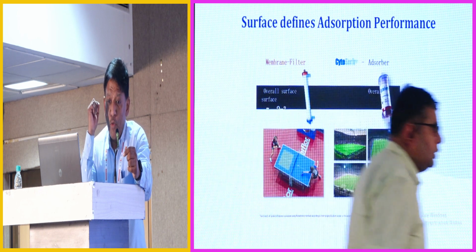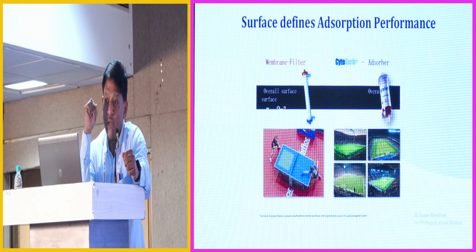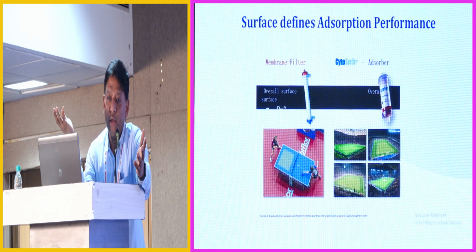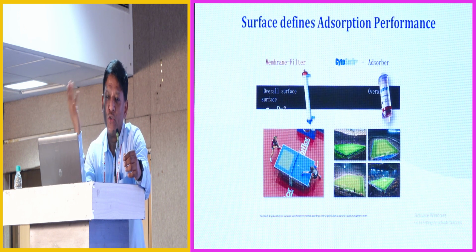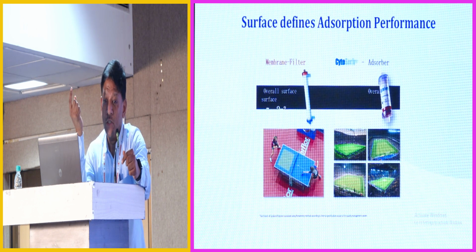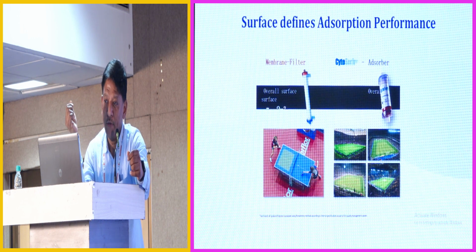So important when you are doing hemadsorption, it's important to know which device has a higher surface area. This is not convection, this is adsorption. So obviously, by common idea, the better the adsorption, you need a higher area. So device selection will be based on your area size. Talk to the company guys, get to the literature, and find which of the devices have the highest areas. No point in selecting a device which has a very low surface area. Adsorption is going to fail there.